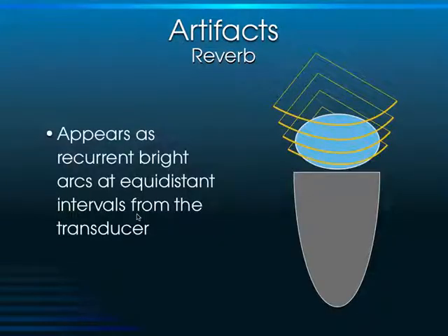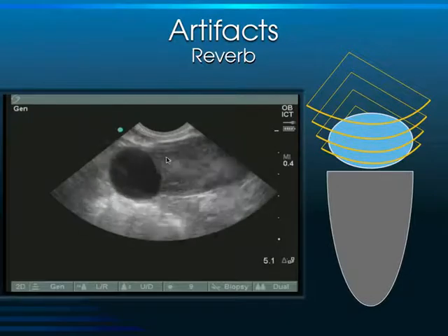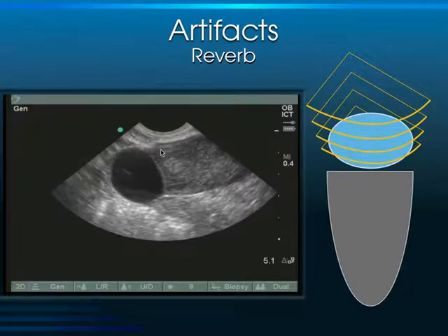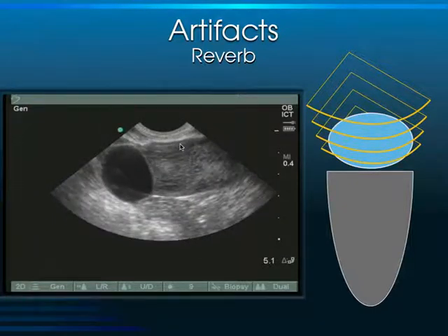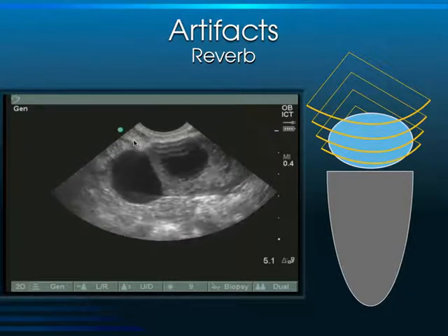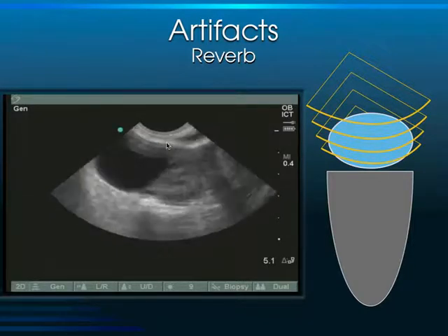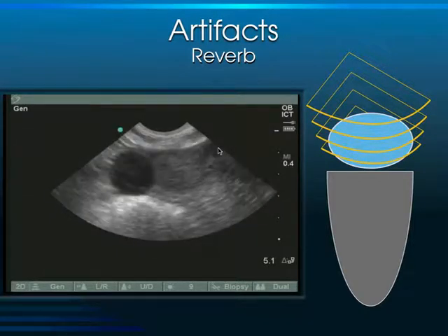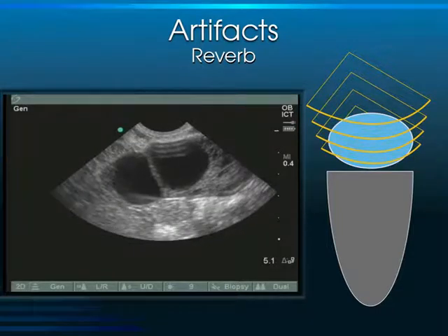Reverberation or reverb artifact appears as equidistant arcs coming down from the top of the probe. It's a natural artifact seen in all transducers. You'll know it's an artifact because these arcs cross the wall of the organ into the adjacent space.